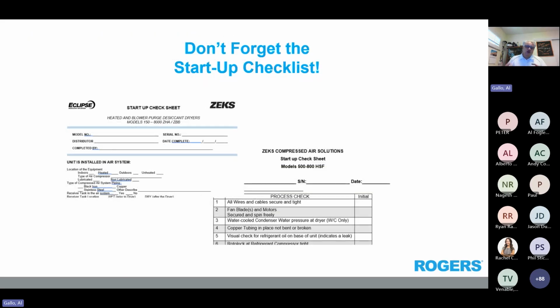And I'm just putting in a quick plug for this. Don't forget startup checklists. Technicians are great people, and they want to do a really good job but are sometimes rushed. They can forget to check something, like doing that tug test on all the wiring in the cabinet, making sure everything is tight, because that stuff can travel across the country. Things can loosen up. So we want to make sure everything is as tight as it possibly can be. And this is just a good reminder for that. Pretty much most of the manufacturers I'm aware of have something for a startup checklist.